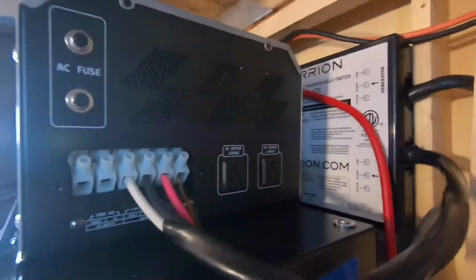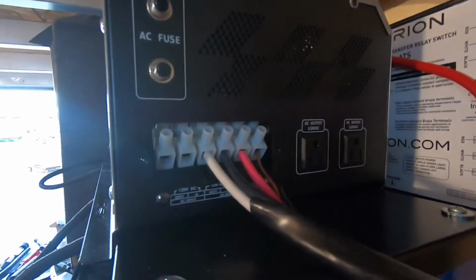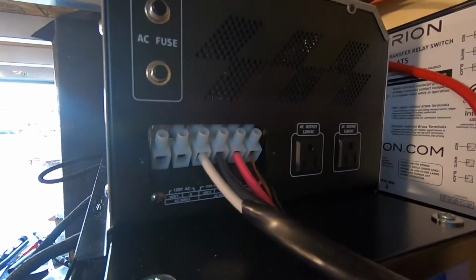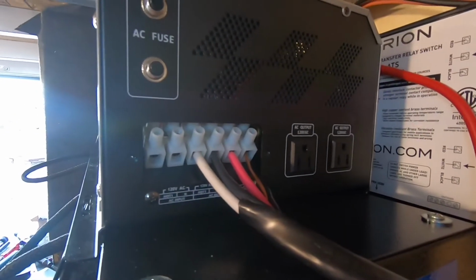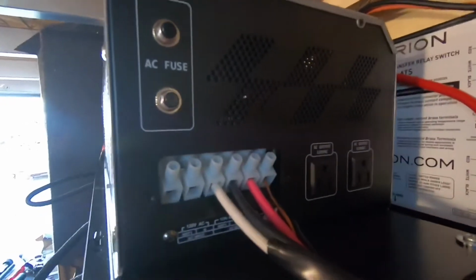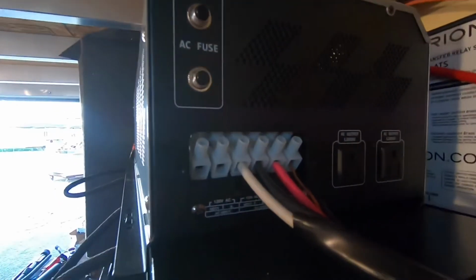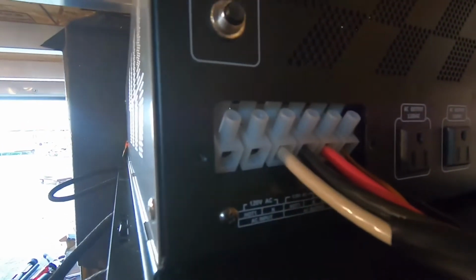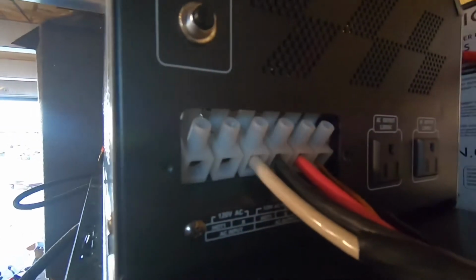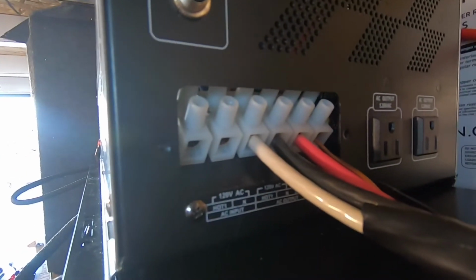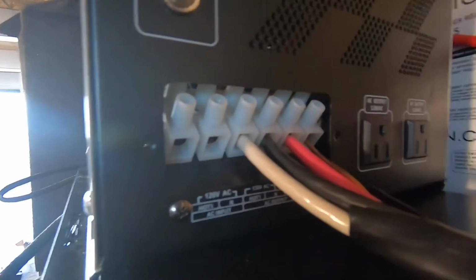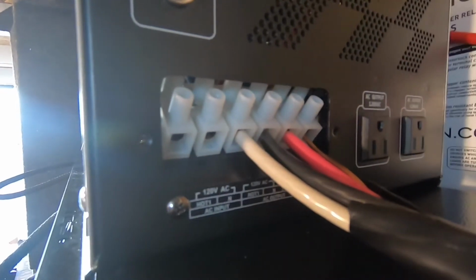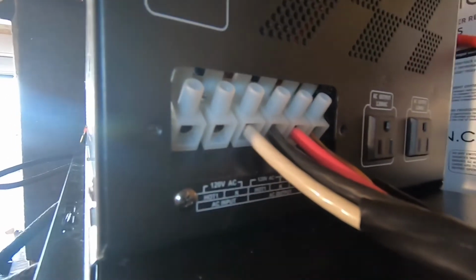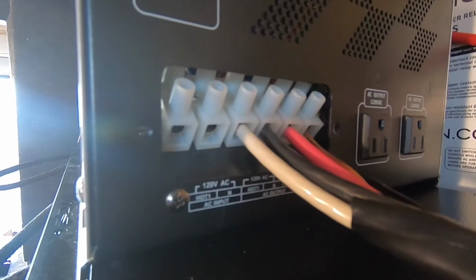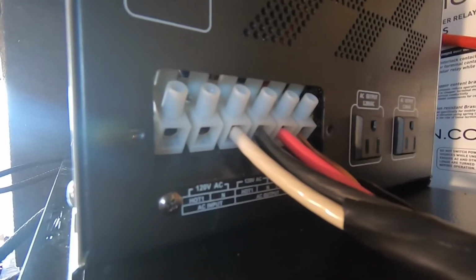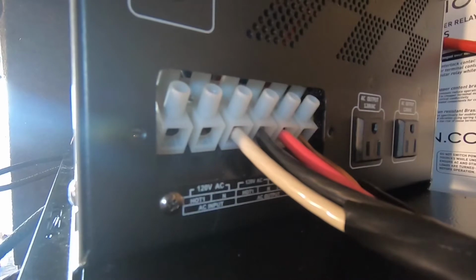The manufacturer wired these terminals incorrectly, where you plug in your 50 amp 4-wire. What should have been hot, neutral, hot, ground, where it was supposed to be neutral was actually hot. If you see the white wire going in now, it's going into a hot terminal, but that white wire is supposed to be neutral.